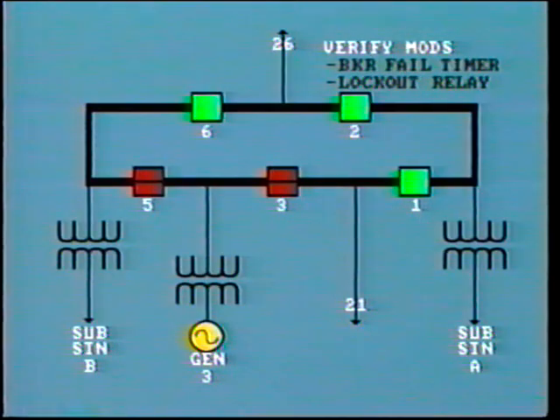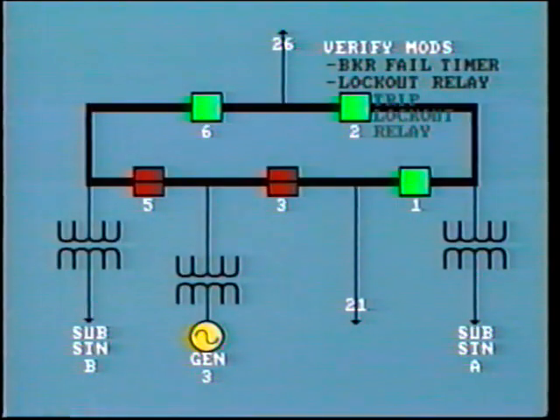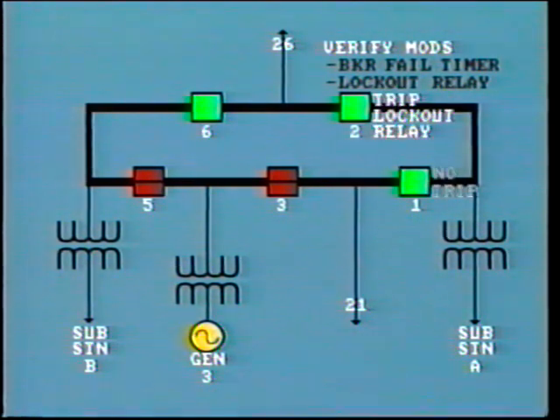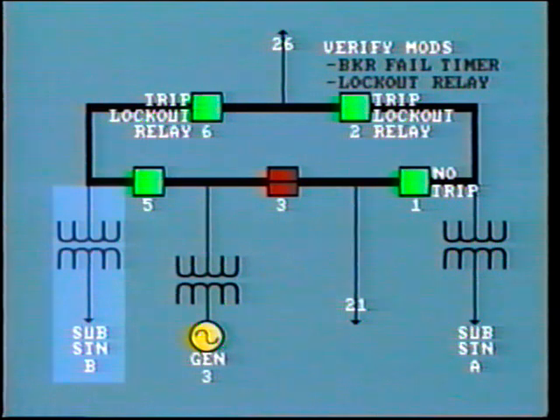So the technicians decided to take a shortcut and trip both lockout relays in order to prove no breaker operation. First, they arbitrarily chose one of the lockout relays. This proved to be the one that should trip breaker 1. Of course, breaker 1 did not trip, as this had been disconnected. They should have stopped right there while the going was good. However, they then moved on to trip the lockout relay associated with breaker 6. The result was an inadvertent trip of breaker number 5, which caused an outage on the feeder to substation B.